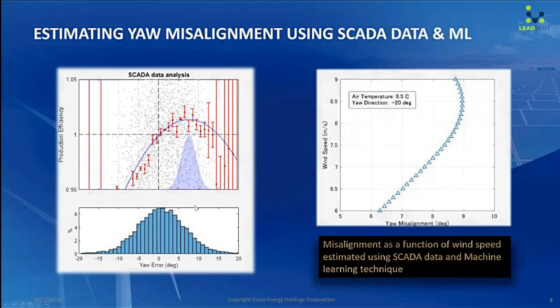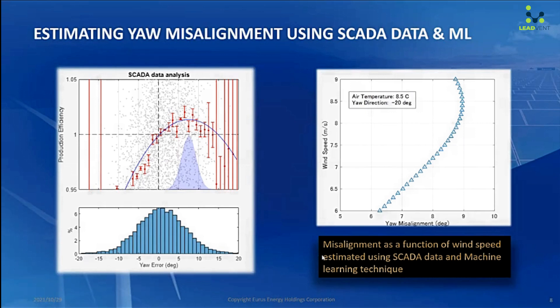Going further, we utilize machine learning techniques. We built a machine learning model based on air temperature, yaw direction, and wind speed. By using this machine learning model for the individual turbine, we are able to estimate the yaw misalignment angle at any wind speed, any yaw direction, and any air temperature. This is because the misalignment angle is also due to the transfer function, which depends on wind speed, air density, and even turbulence intensity, which might depend on the yaw direction.